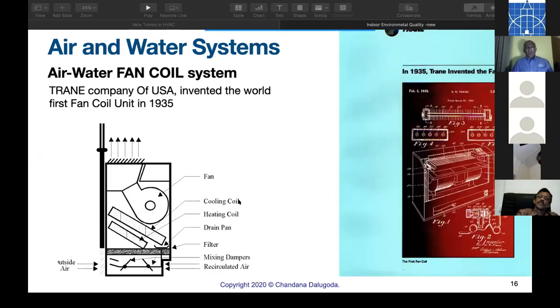Now, this fan coil was first introduced by Trane Company, USA, in 1935. I have to remind you that air conditioning was invented by Dr. Willis H. Carrier in 1902. Centrifugal refrigeration, Dr. Willis H. Carrier invented. So the fan coil came into existence from 1935. It has a cooling coil, an air filter, air sucked through this way, fresh air intake here, and a fan. Sometimes you have draw through or sometimes blow through. Normally fans are behind, so pushing through the coil, you call it blow through.